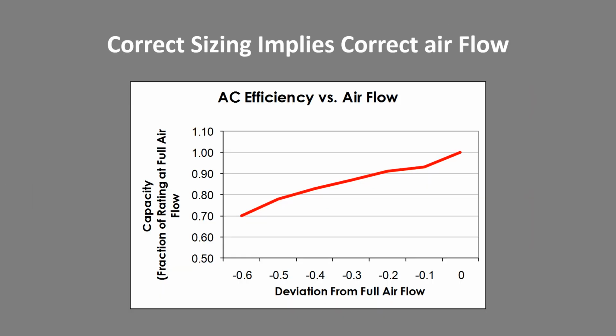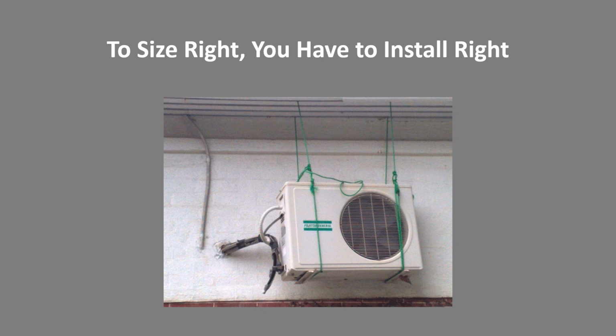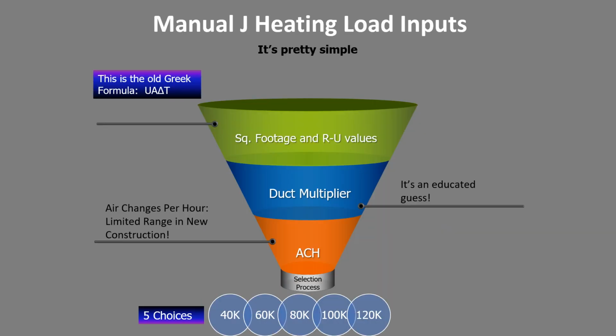Correct sizing implies correct airflow. If you are going to size right, you have to install right. If we look at this graph right here, we can see that at full airflow, we have 100% of the capacity of this particular system. As we get, say, 20% low airflow, we're down to 90% capacity. Boy, if we get 30% low airflow, we're around 85%. So if you're going to size right, you have to install right. We all have funny pictures like this around the shop, but that adage is very true.